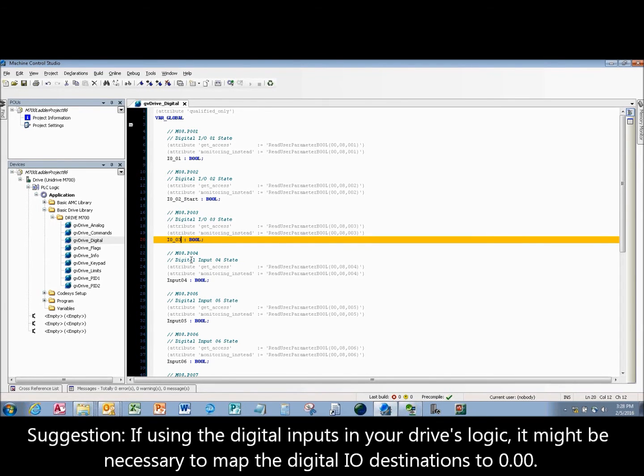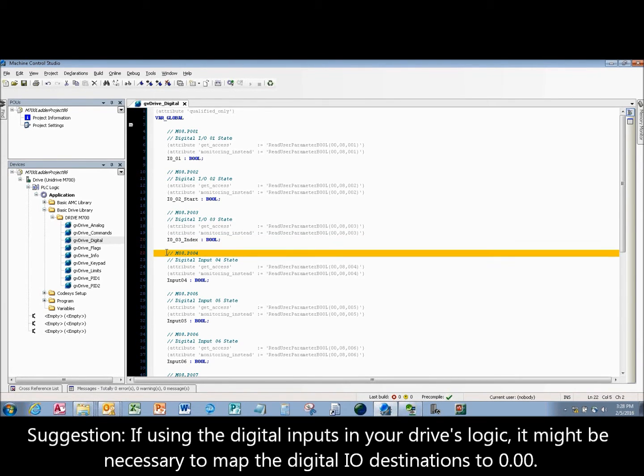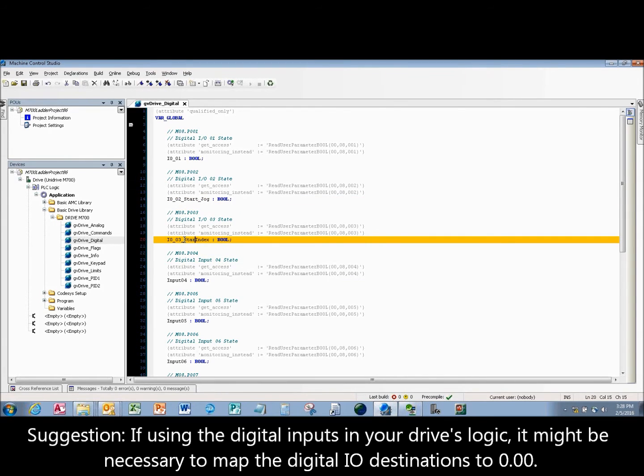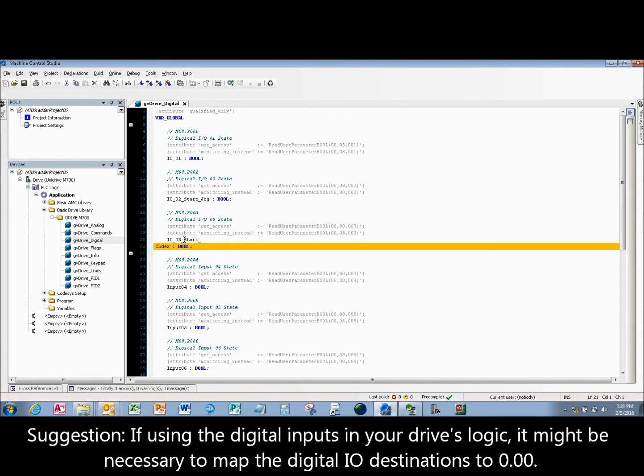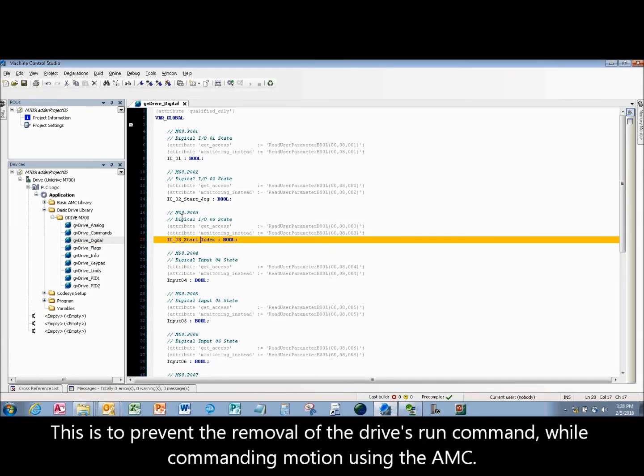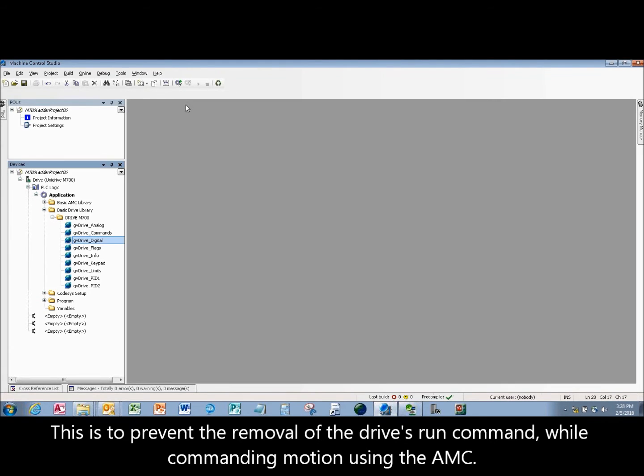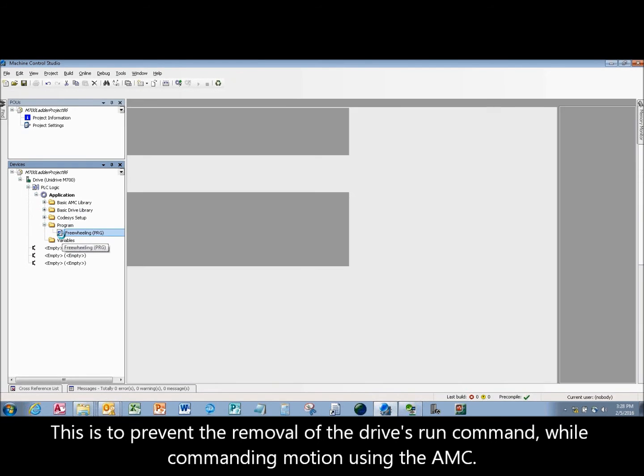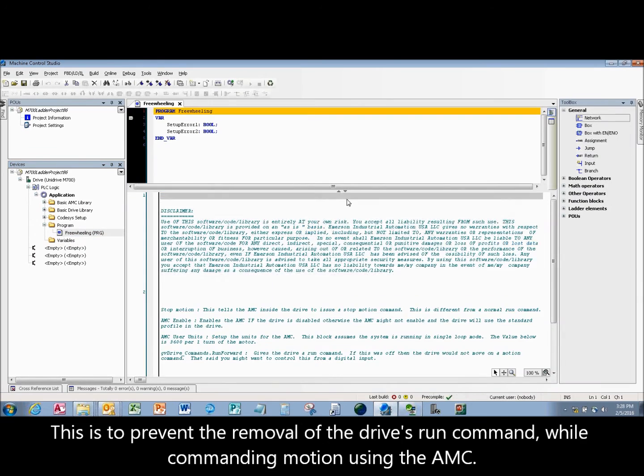Suggestion: if using the digital inputs in your drive's logic, it might be necessary to map the digital I.O. destinations to 0.00. This is to prevent the removal of the drive's run command while commanding motion using the AMC.